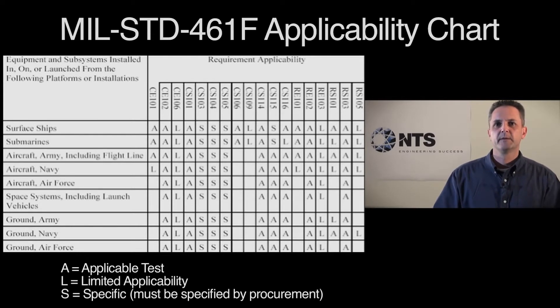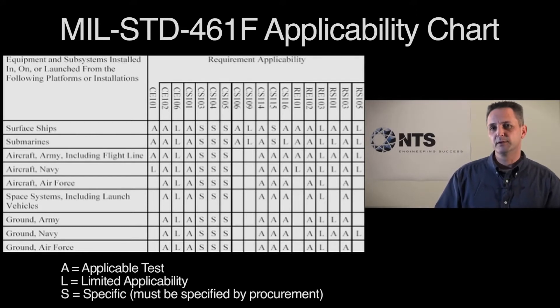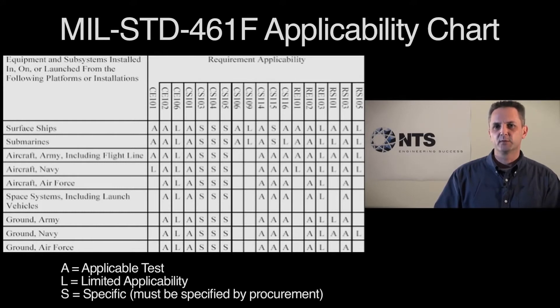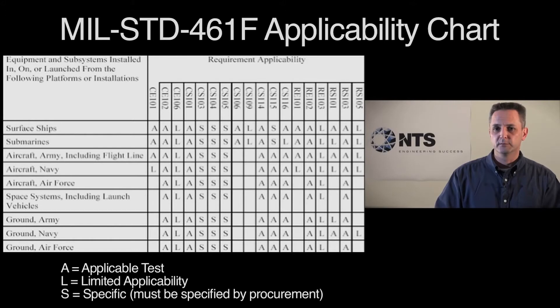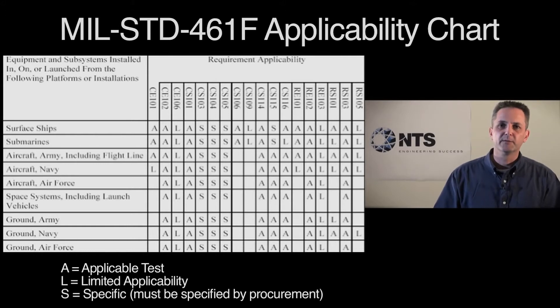Along the top of the chart lists all of the applicable tests in MIL-STD-461F. For example, the top line shows surface ships — equipment that could be installed in surface ships, regardless if it's topside or below decks. CE-101 and CE-102 would be applicable tests. CE-106 is shown as an 'L', which stands for limited applicability. CS-103, 104, and 105 are specific, mainly dependent on the type of equipment. CS-109 is a limited applicability test. CS-114 is an applicable requirement. CS-115 is specific to the equipment. CS-116 is an applicable conducted susceptibility test. RE-101 and RE-102 are both applicable. RE-103 is limited. RS-103 and RS-101 are both applicable, and RS-105 is in limited application.